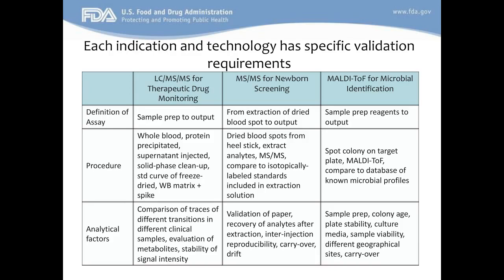So we can start with the MALDI-TOF on the right. This is a device which uses a colony from the microorganism, which is spotted on a plate. Some of the important things that were required to clear this device were understanding the effect of the age of the colony, the stability of the colony on the plate, and what kind of culture media was used to develop the sample for the spotting. So these are very device-specific and analyte-specific questions that needed to be addressed by the manufacturer before clearance of this device. The other two devices were more similar in the sense that they're LC-MS devices that are used to quantify chemical compounds or metabolites.